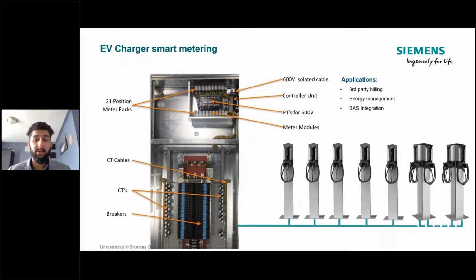This requires some metering in the panel to measure the kilowatt hours each charger is consuming, and it can be used with building management and automation systems so you can download the data to servers and read the kilowatt usage of every EV charger. This gives a better understanding of the chargers' impact on your electrical infrastructure, and you can also use a Measurement Canada approved meter for billing purposes by a third party.